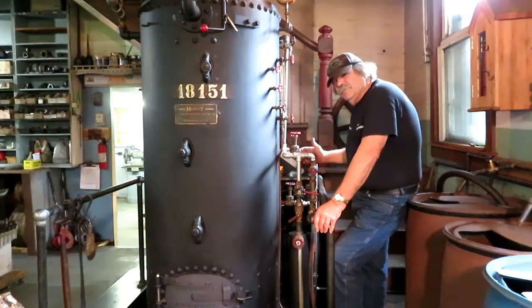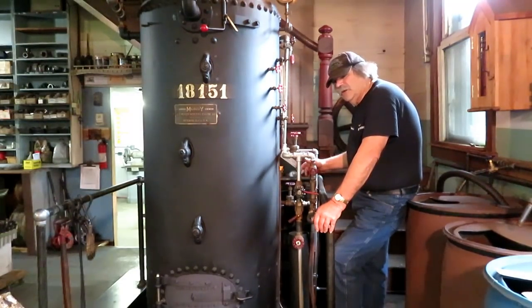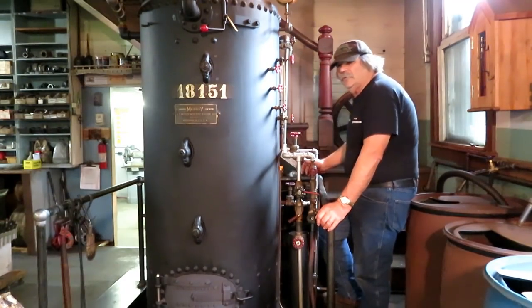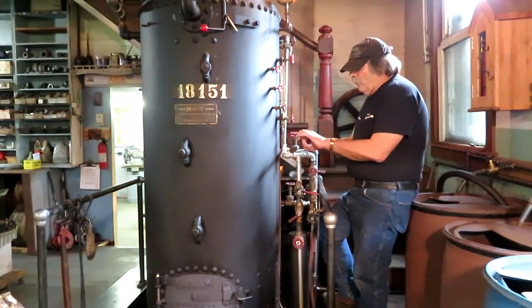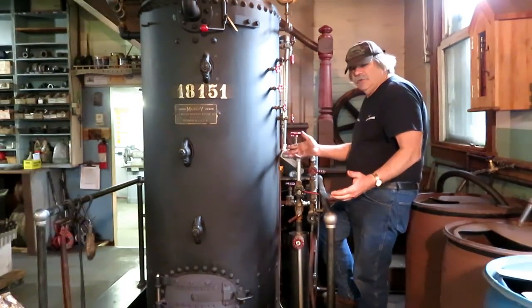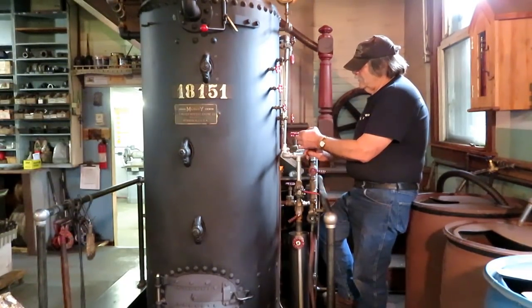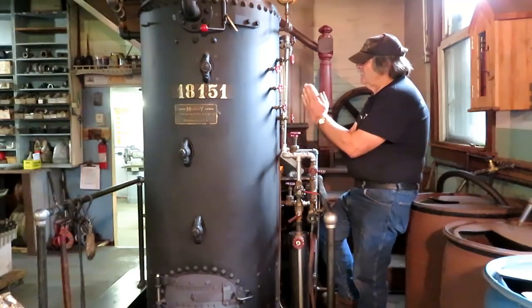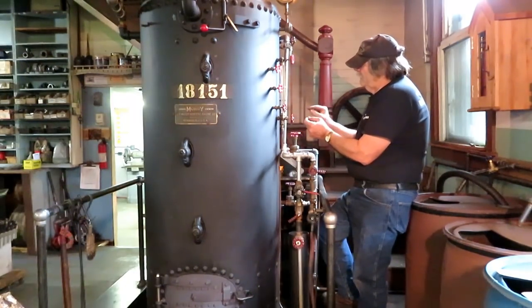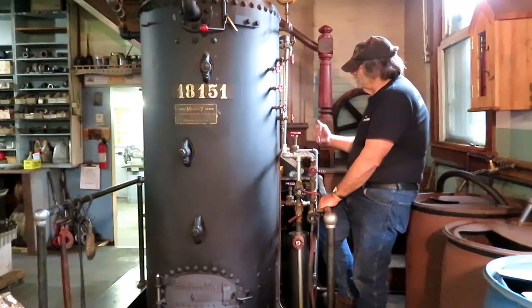But just to briefly, simply tell you what I have read and what I know firsthand and what in my mind is actually happening here, you've got basically a siphon set up. If you've ever had one of those boat balers that will bail your boat out with a garden hose, where you hook the garden hose up and a stream of water coming out will pull water in from the side, you waste a lot of water that way, but it does pull the water out of your boat. Well, that's a siphon. And anytime you have a liquid or a gas running through a pipe and you put another pipe on it sideways and there's a constriction in there, a Venturi, it will create a vacuum on this side pipe. Well, that's what happens here. You turn the water on, and you turn the steam on, and it pulls the water up.